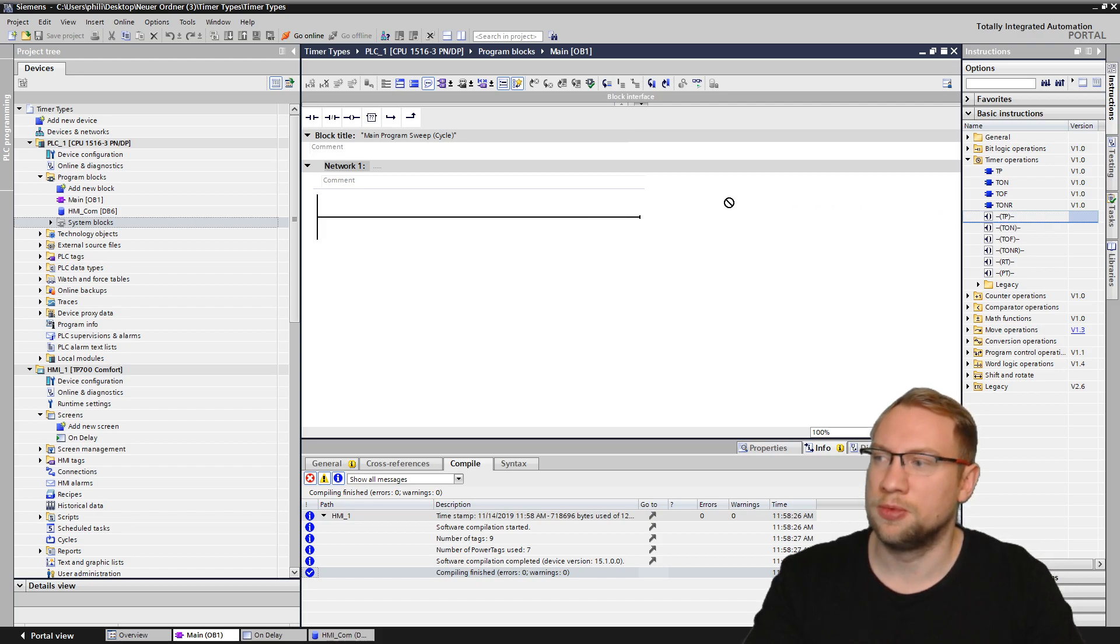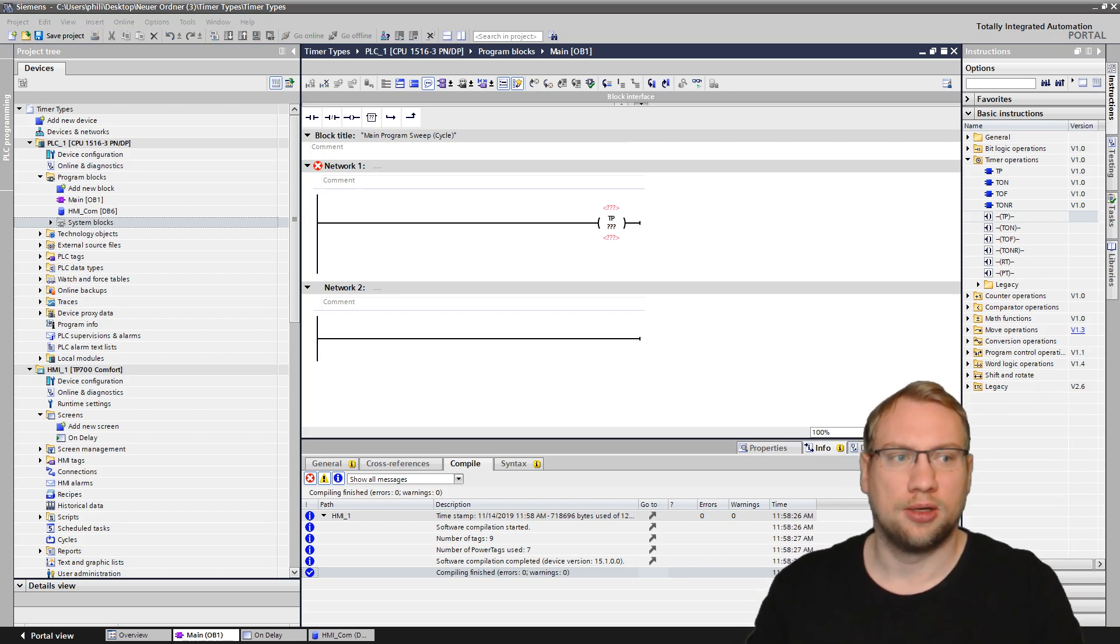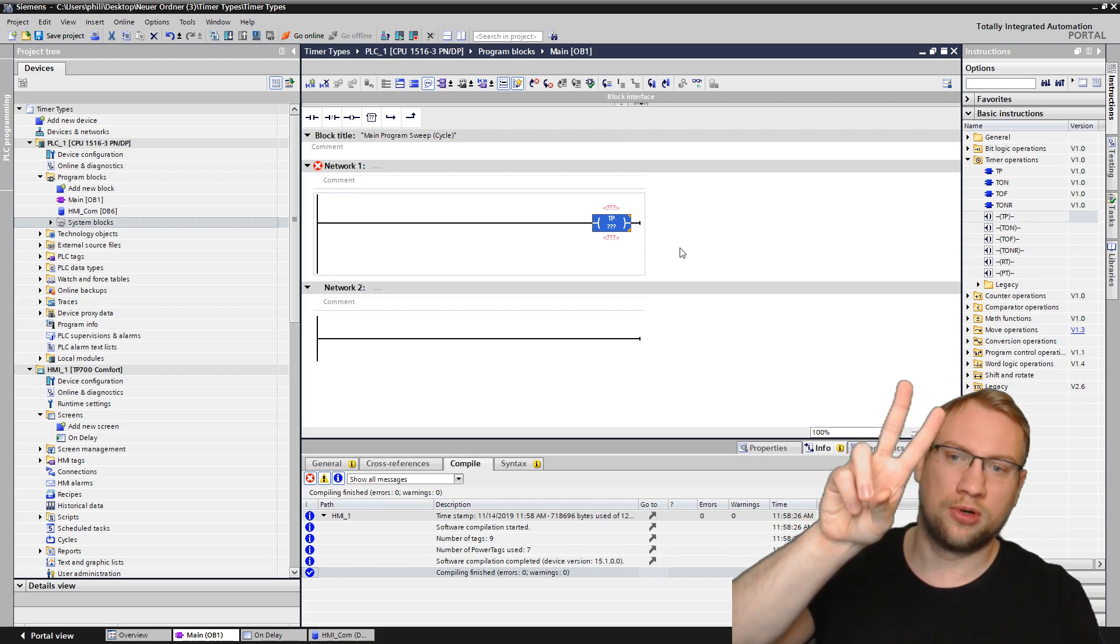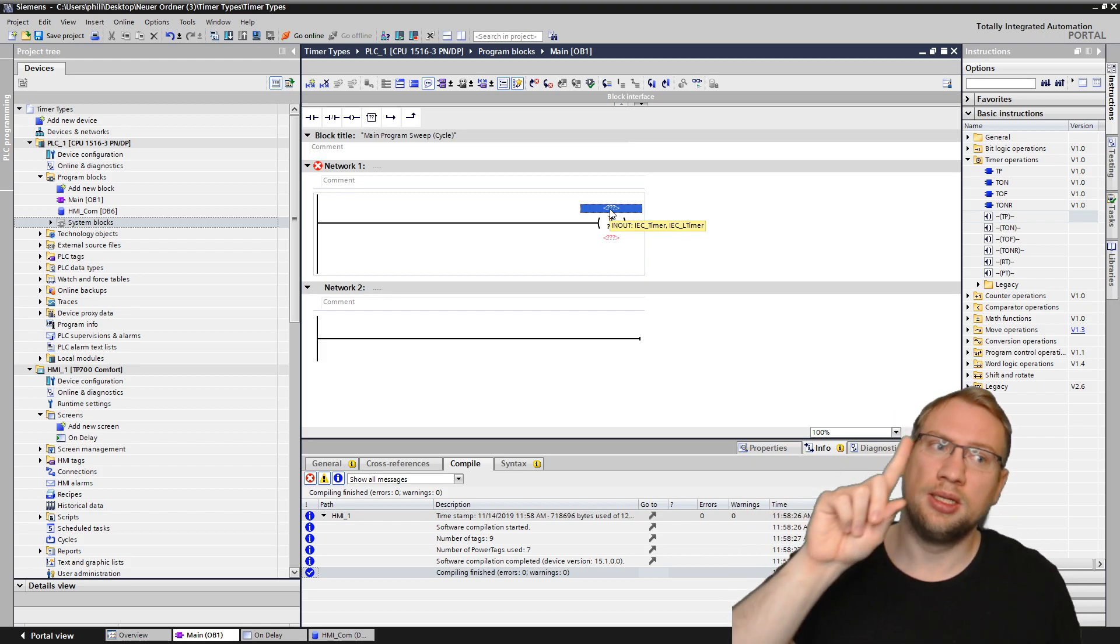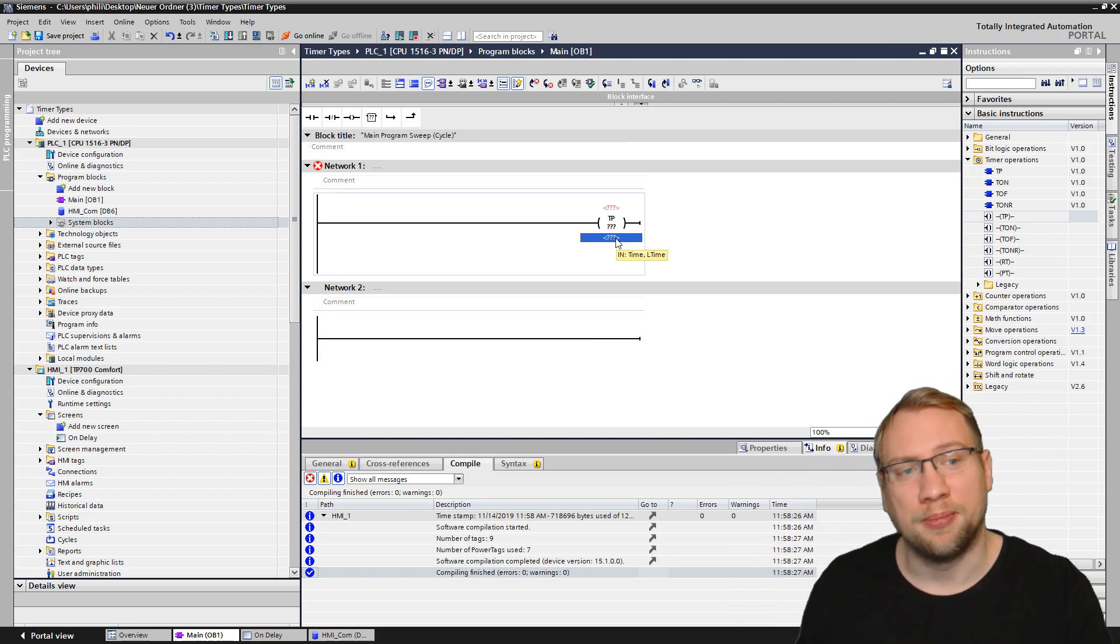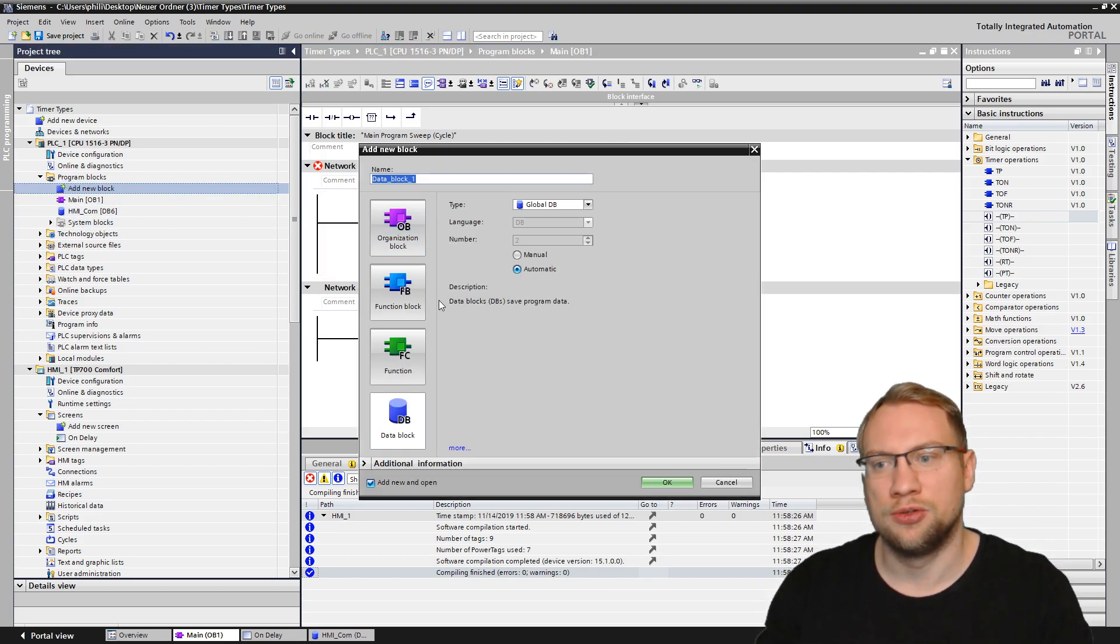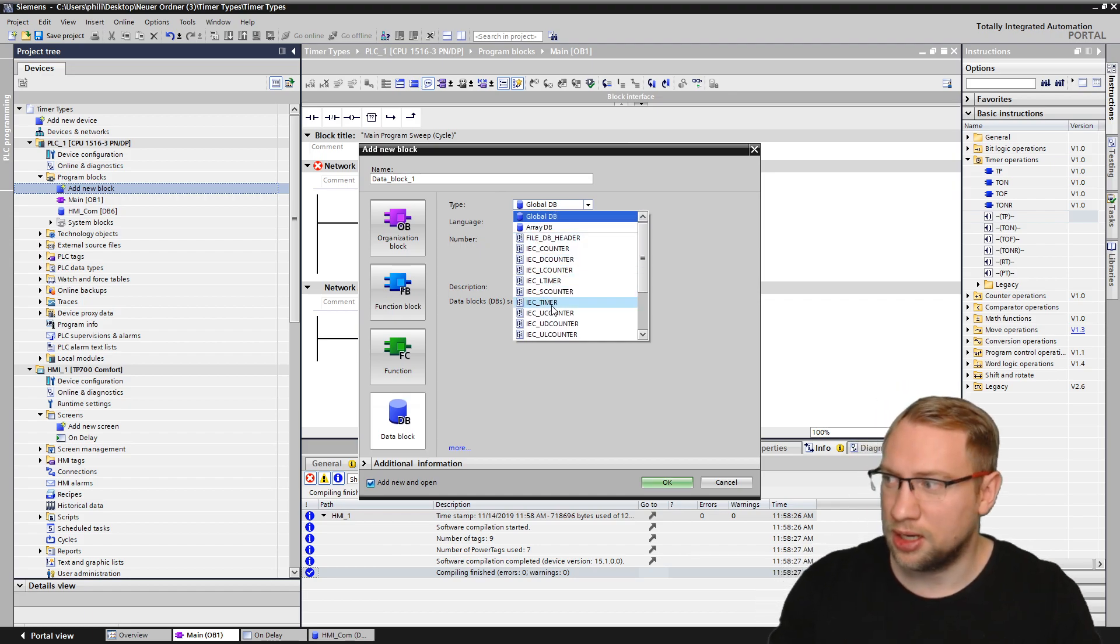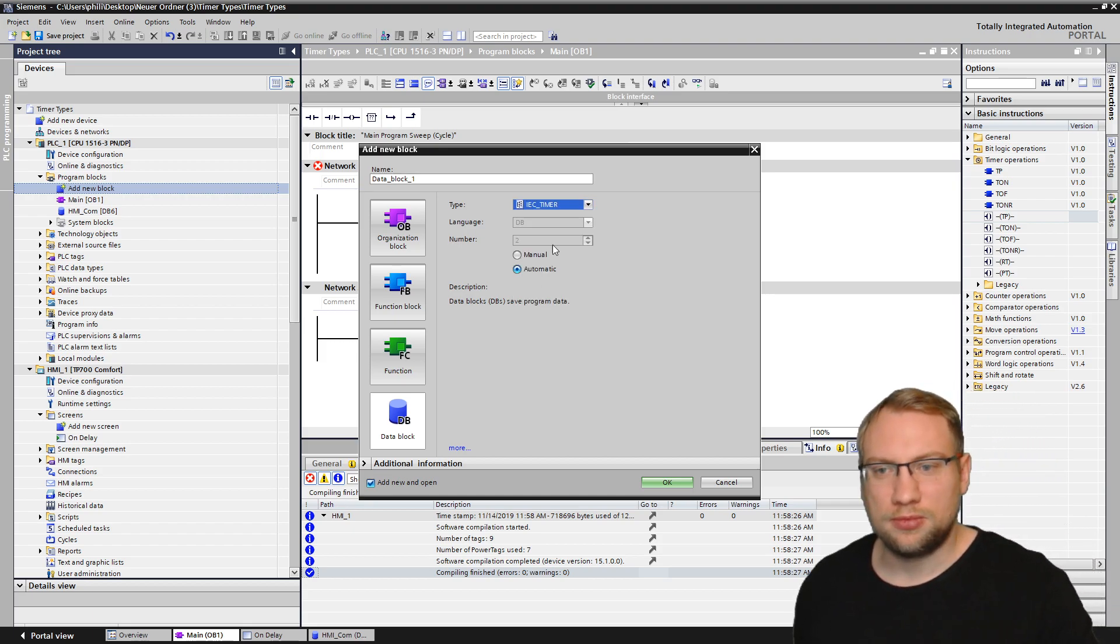So let's just drag and drop this TP on here. And you will see it looks like a program, like an assignment. And this TP right now asks for two things. It asks for a data block that it needs to store all its data, and it needs the second thing, a time. So the data block is really just you create a new block, add a new block. It's a data block. And there you have either IEC timer, that's the type, or IEC long timer.